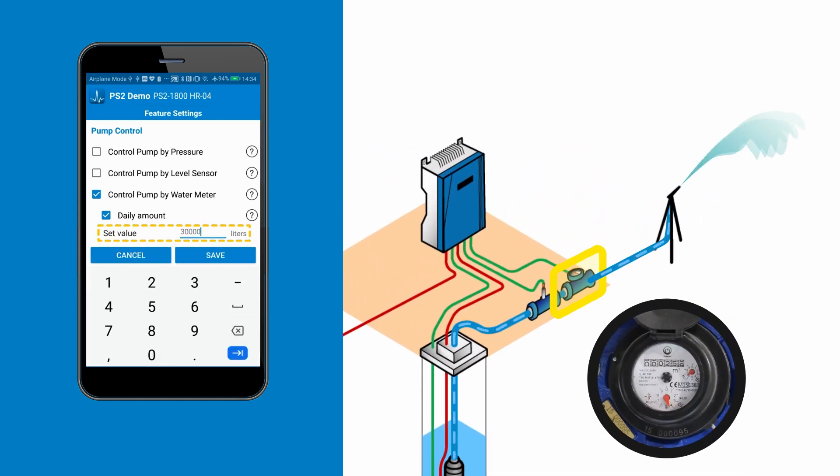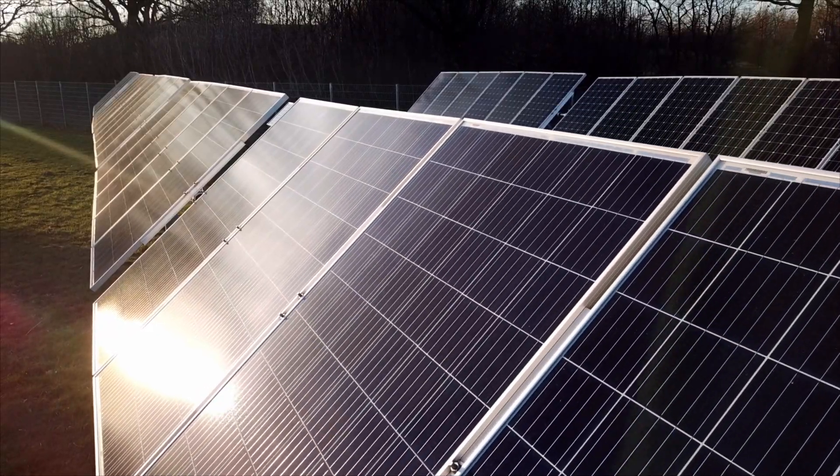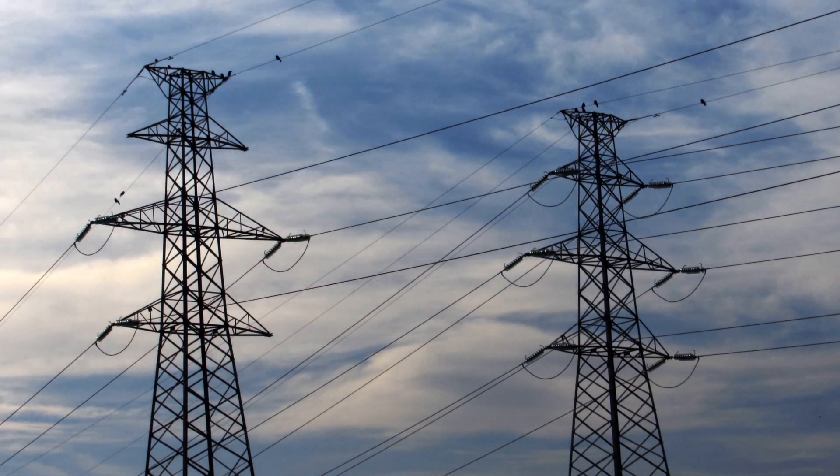You simply set a daily amount and when the daily amount is reached, the pump will stop. The daily amount feature works really well in hybrid pumping situations. The water is pumped by solar and if the daily amount cannot be achieved by solar, then the remainder is topped up from grid or generated power automatically.